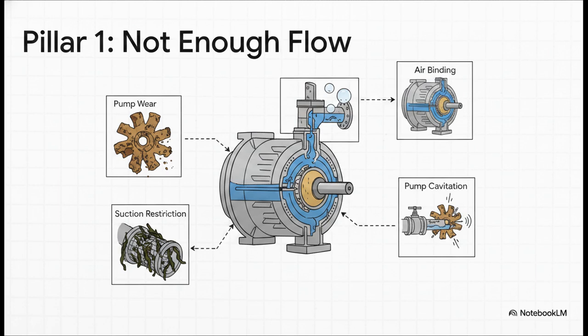Let's talk about Pillar 1, not enough flow. This is simple, right? The water isn't moving fast enough to carry the heat away. Now, the pump motor might be running, but that tells you very little. The pump's internals could be worn out, you could have an airlock in the casing, the suction strainer could be choked, or a bypass valve could be leaking internally. Remember this, a running pump is not the same as a performing pump.